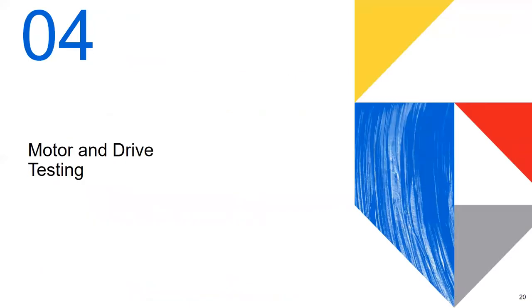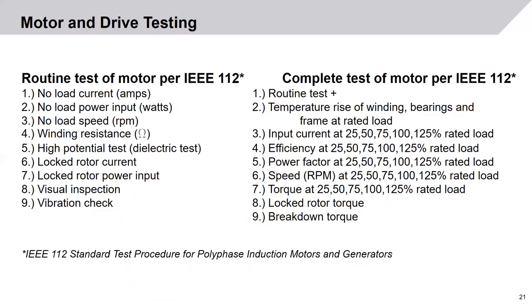Motor and drive testing. Motor testing is defined by IEEE 112, the standard test procedure for polyphase induction motors and generators. During routine testing, a motor will go through no-load current, no-load power, and speed measurements; winding resistance in ohms; a high-potential test; lock rotor current and lock rotor power input; visual inspection; and a vibration check. A complete test includes those nine items plus temperature rise of windings, bearings, and frames at rated load.